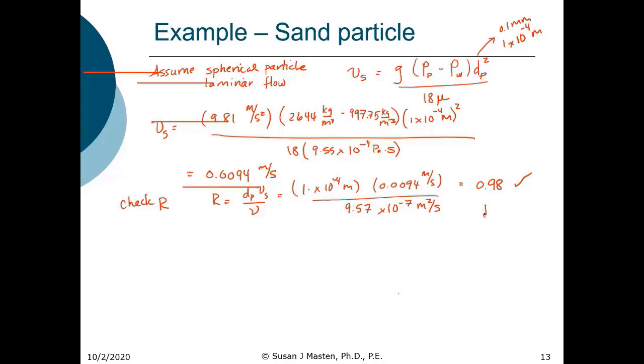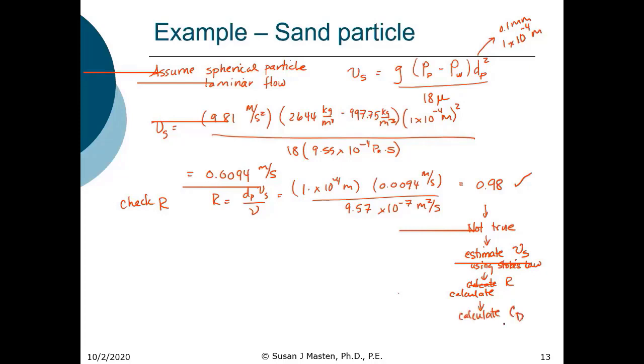If the Reynolds number check had failed, you would use an iterative process: first estimate terminal settling velocity using Stokes law, then calculate Reynolds number, then calculate the coefficient of drag using the full equation, then calculate a new terminal settling velocity, and continue until it converges. We will actually have to do this when we move into filtration hydraulics.